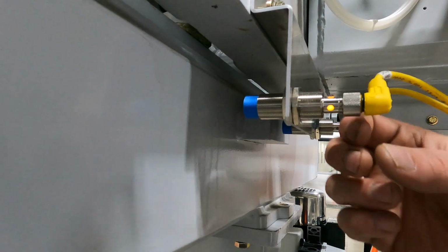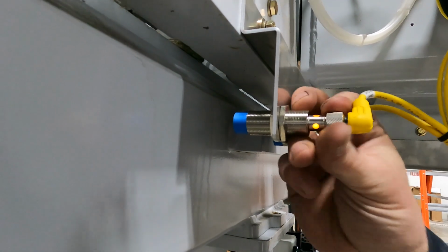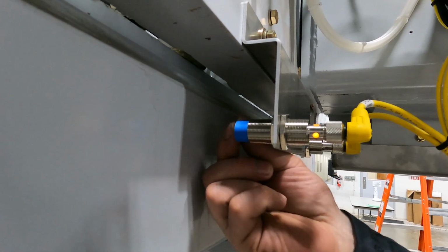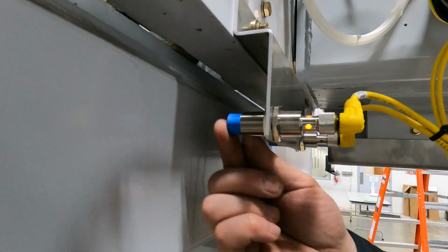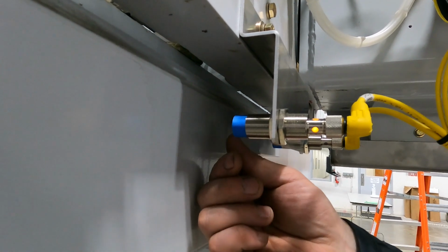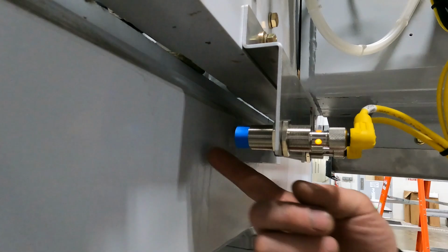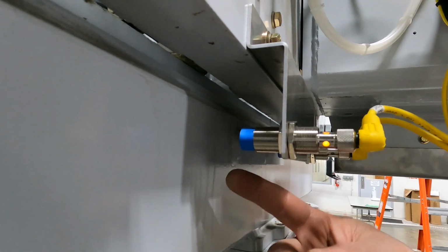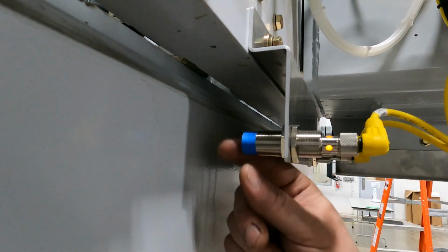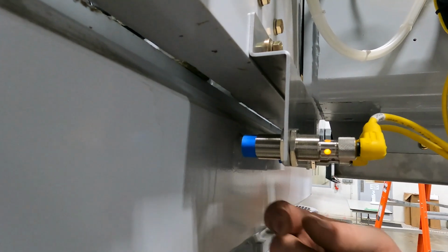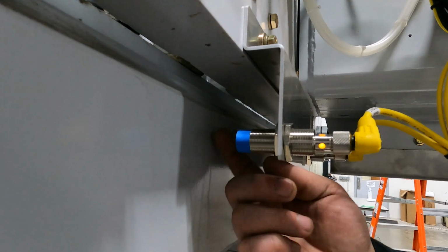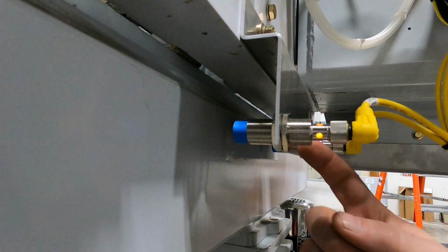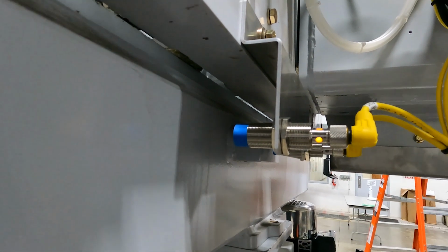If your lights do not come on and your cable's not loose, the next step would be to make sure your proximity sensor, the tip of the sensor here, is clean. If it's real built up with dust and dirt and stuff, that can cause the prox to read incorrectly. Make sure there's no damage at all done to it. If it broke off or anything like that, that will cause it to malfunction also. If you're not seeing any damage, you cleaned it up and it's still not working, then your issue is going to lie in the prox being bad or the cable going back.